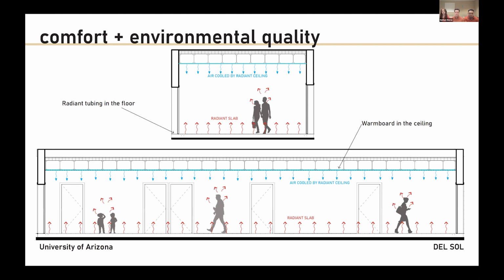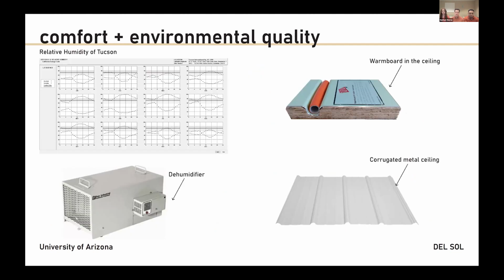We're investigating whether it's better to insulate under the slab or around the perimeter, considering comfort, cost, and embodied carbon. Tucson does have humid months during the summer, so even though the radiant system is much more energy efficient than forced air, it requires dehumidifiers. Without them, there would be condensation whenever the dew point is higher than the 60-degree radiant tubing, which would likely cause mold to form.